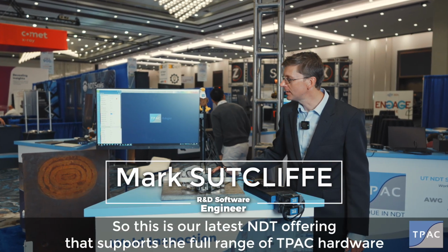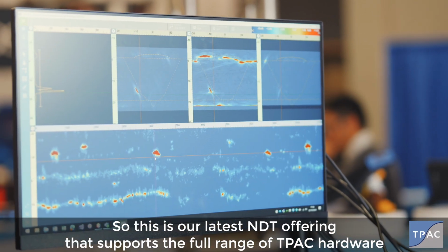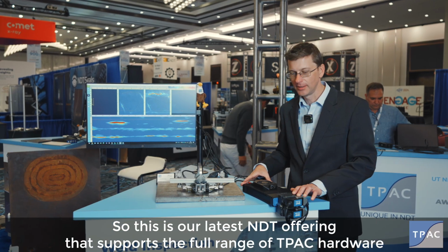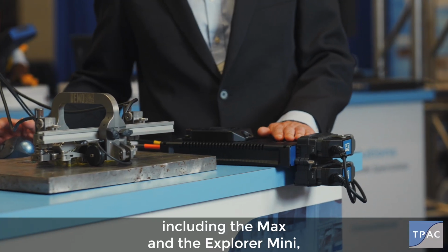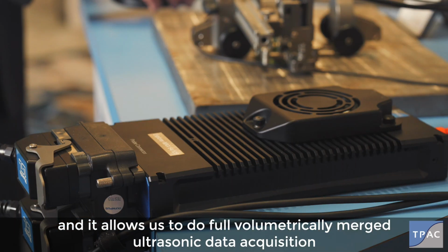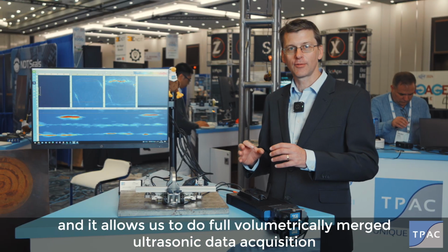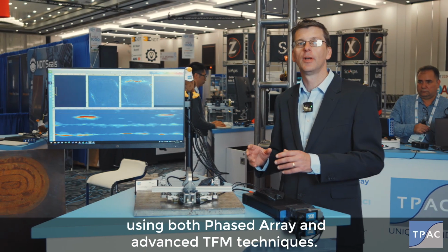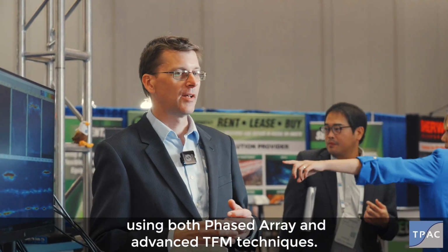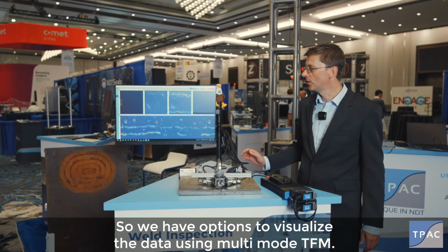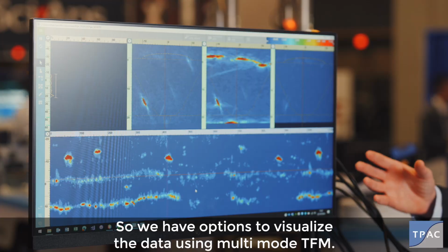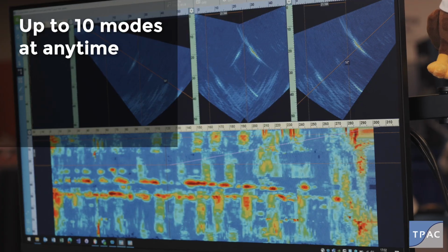I'm representing TPAC today and I'm going to talk about the TPAC Adagio software. So this is our latest NDT offering that supports the full range of TPAC hardware, including the Max and the Explorer Mini, and it allows us to do full volumetrically merged ultrasonic data acquisition using both phase array and advanced TFM techniques. So we have options to visualize the data using multi-mode TFM.